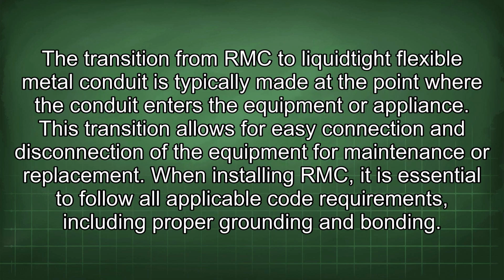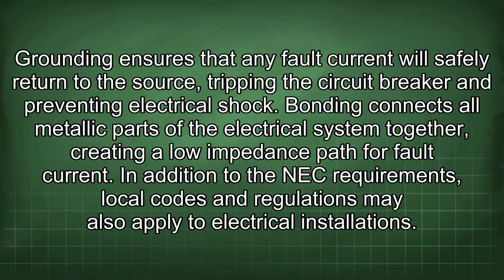The transition from RMC to liquidtight flexible metal conduit is typically made at the point where the conduit enters the equipment or appliance. This transition allows for easy connection and disconnection of the equipment for maintenance or replacement. When installing RMC, it is essential to follow all applicable code requirements, including proper grounding and bonding. Grounding ensures that any fault current will safely return to the source, tripping the circuit breaker and preventing electrical shock. Bonding connects all metallic parts of the electrical system together, creating a low impedance path for fault current. In addition to the NEC requirements, local codes and regulations may also apply to electrical installations.